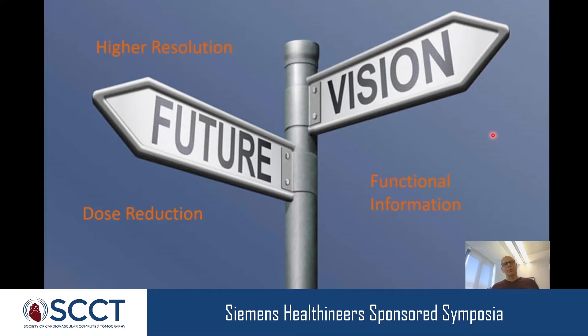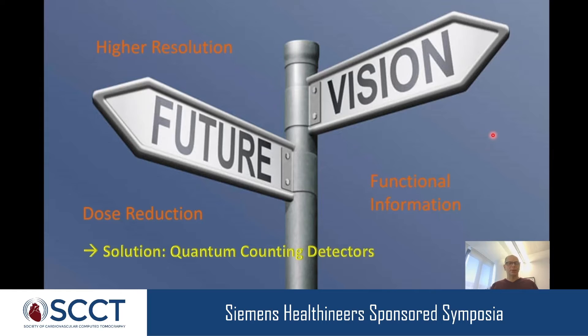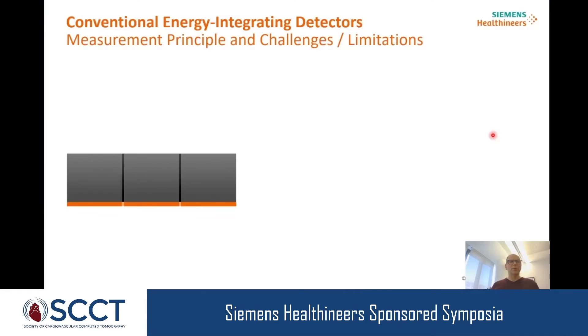However, if we want to really expand the level of resolution, reduce radiation dose further, and always have functional information available, the current energy integrating detector technology — used in all CT scanners today — cannot accomplish that. The solution is the introduction of photon counting detectors. Before explaining the principle, let me briefly review how we measure X-ray quanta in a conventional energy integrating detector.